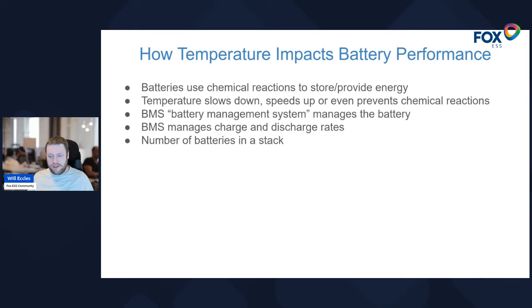The number of batteries you have in series within your installation will directly impact whether you notice, or how much you notice, this temperature impact. Because the charging and discharging amps times your voltage equals the kilowatts in and out of the battery that you'll see on the app. If you have a smaller battery setup that's of a lower voltage, you'll have to use more amps to get the same kilowatt output than you would with a system that has a higher voltage, as an example. So we'll come back to that because that's an important point.